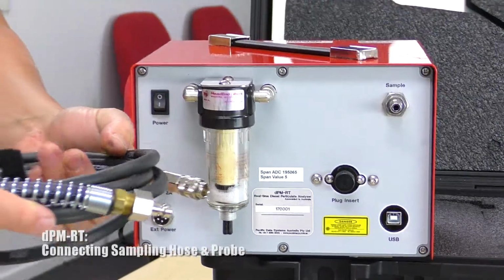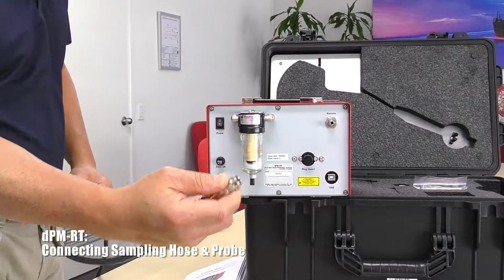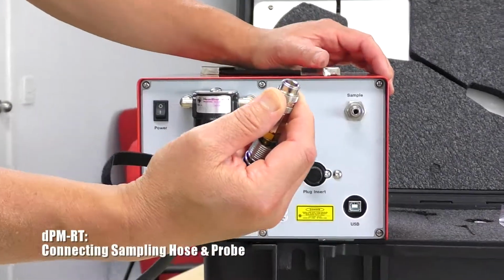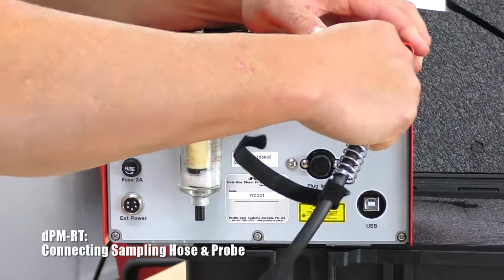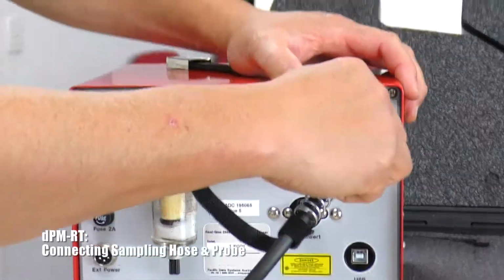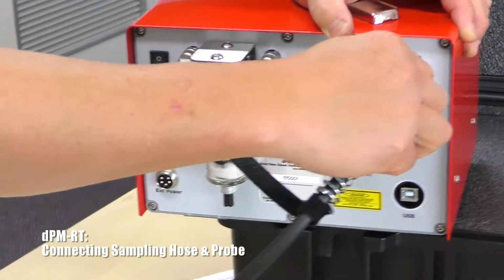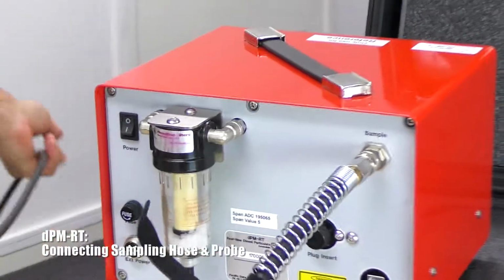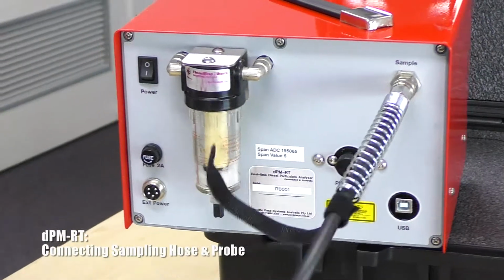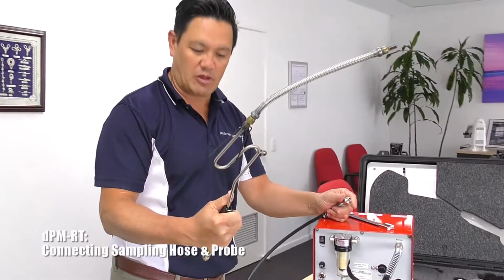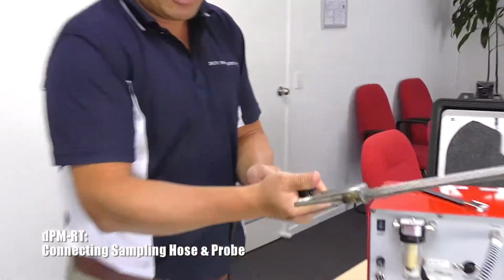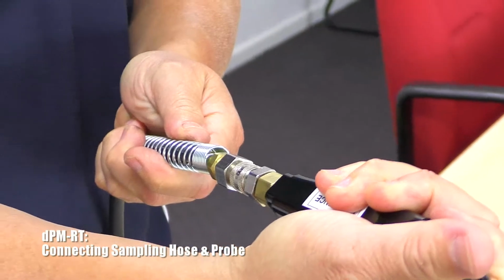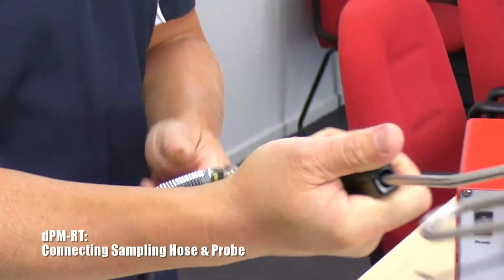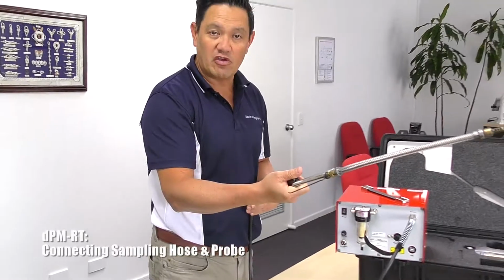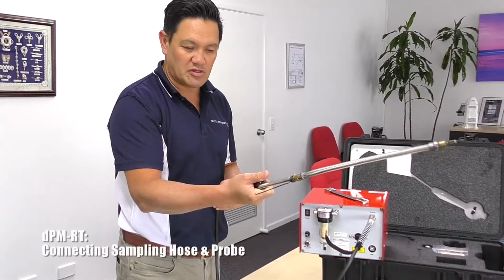This is the sampling hose that was indicated earlier. It's an easy, quick connector. Slide the collet back on the hose, connect it up to the sampling port, give it a small tug, make sure that it's fitted and connected. Grab the other end of the hose, grab your sampling probe, and then connect up the sampling probe to the sampling hose.